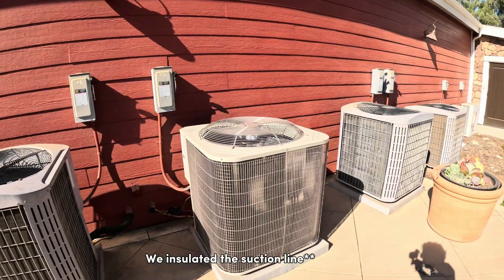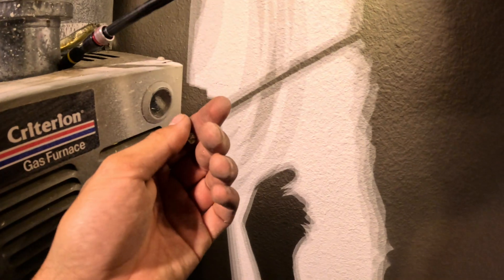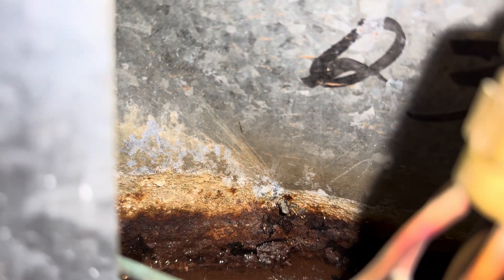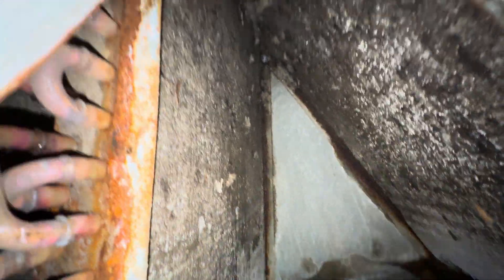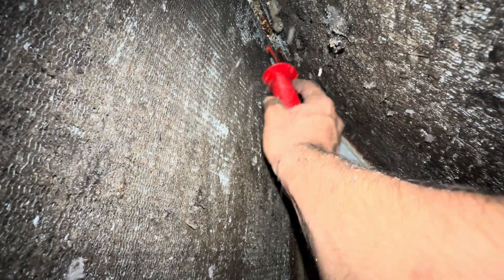Alright guys, we're all wrapped up here. I'm going to go do the pan treatment and evap cleaning right now. See how that's going — that was getting all trapped inside of the primary line, causing it to leak throughout the entire system underneath, causing water damage.